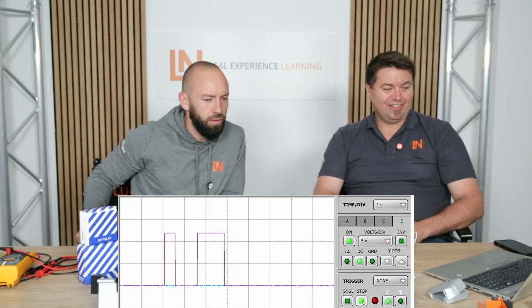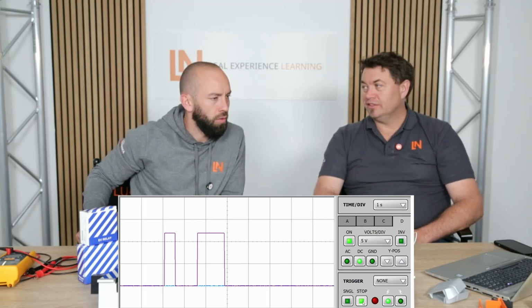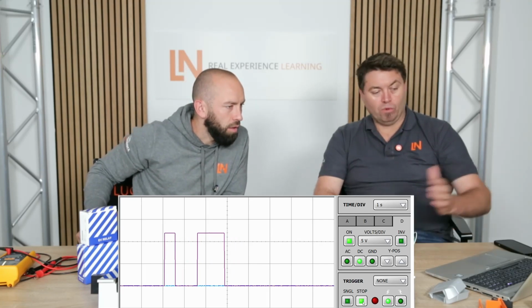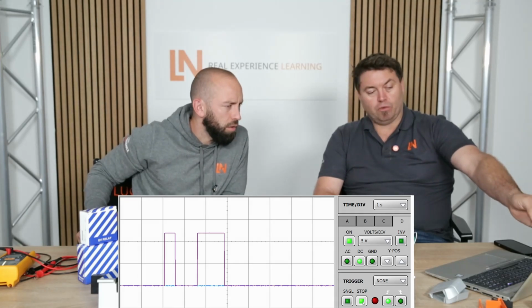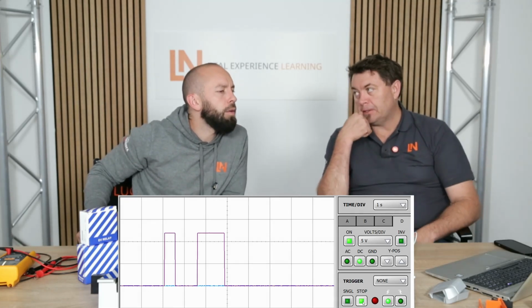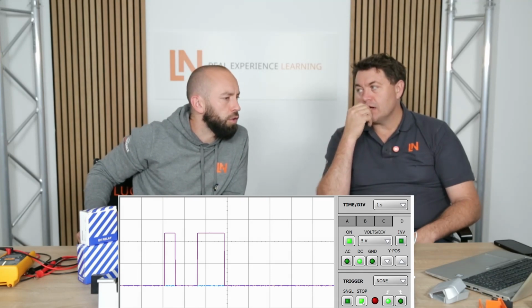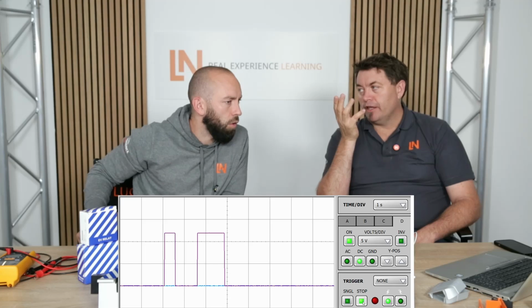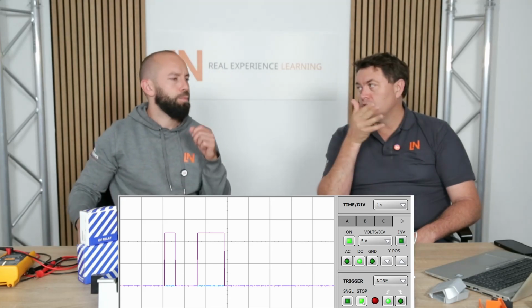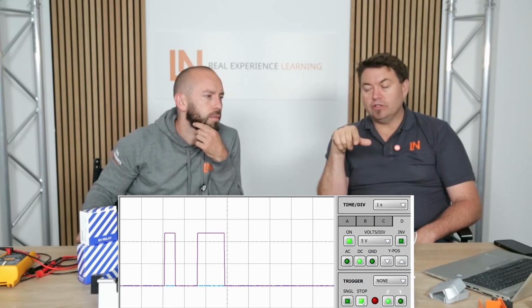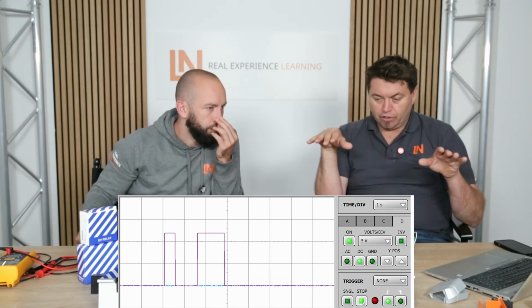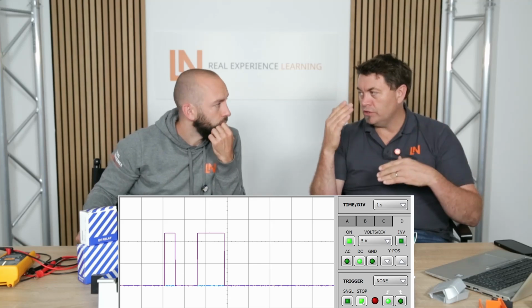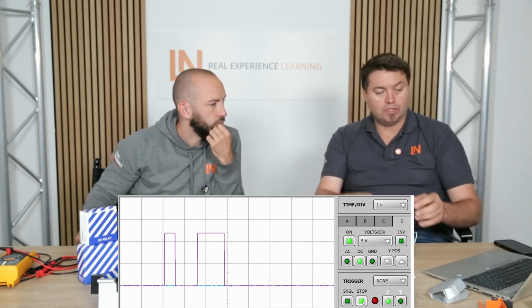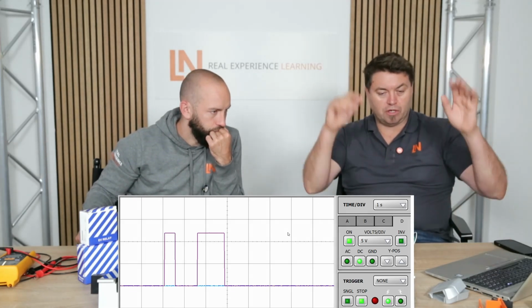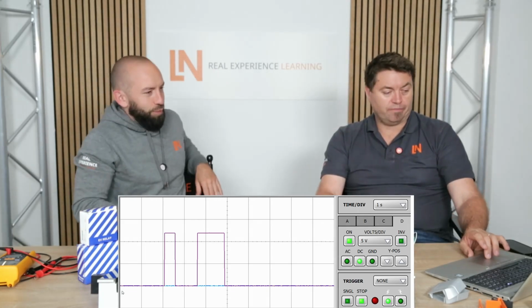Oh, what's that now? Nothing happened at all. Which one do you think that is? What do we see there? We see the pre-charge relay, right? What normally comes on after the pre-charge relay? We have an issue with the high voltage minus relay, it can't switch it on or can't reach it. Before we didn't control the plus relay, now something's happened here on the negative side. Therefore we have no voltage at zero closed circuit, zero high voltage or DC link voltage. We just see that, and the system's like, okay, nothing. Can't do anything here.